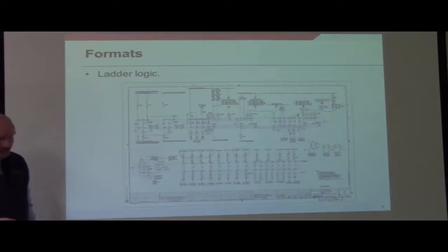This is an example of what ladder logic looks like. We've got a large microprocessor-based relay here that has a number of inputs and outputs. It breaks here and starts back up here, with quite a few inputs and outputs. The various control voltages are these lines up above, labeled, and a line down below for the negative, so you have positive on top and negative on the bottom.